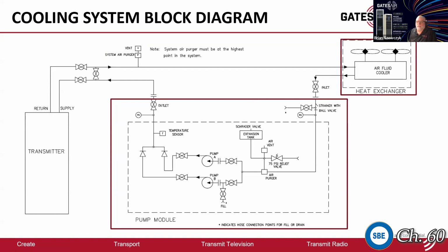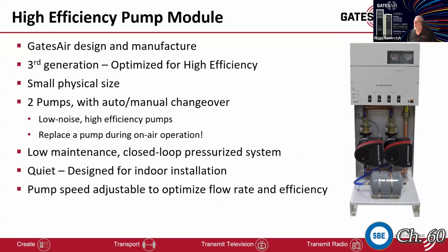And the heat exchanger is typically mounted outside. In some places, such as World Trade, we don't actually use a heat exchanger. We connect to the building's chilled water, and World Trade actually takes that energy and uses it for heating domestic hot water and heating and cooling.